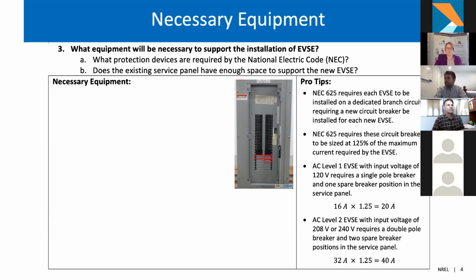Are there any additional questions? As in the example before, if you're looking at say 6 ports, you potentially need 6 new branch circuits because you're installing 6 new EVSE. So if you're installing a dual port EVSE, according to the National Electric Code, you should technically have 2 separate branch circuits powering those. Now some EVSE provide power sharing, so you only supply it with 1 circuit breaker, and if only 1 vehicle is plugged in it gets the full power. If both ports are occupied by 2 different vehicles, each vehicle gets half the power. That's a good way to avoid expensive infrastructure costs. If you're trying to install a lot of EVSE and don't want to upgrade your service panel, you could cut your system in half with power sharing options. That's a feature available in some EVSE.